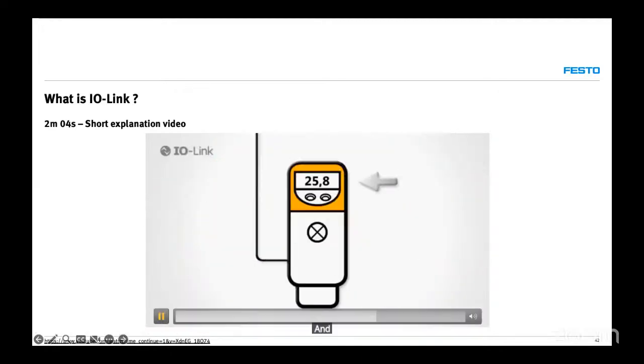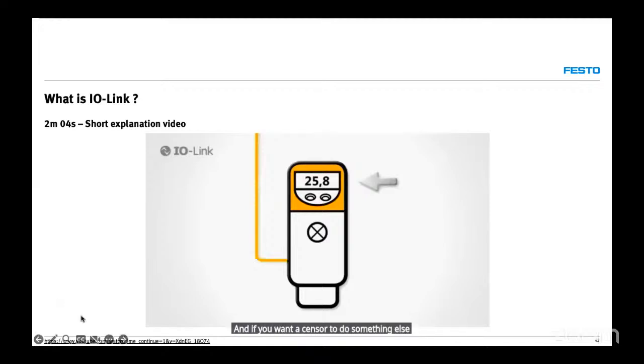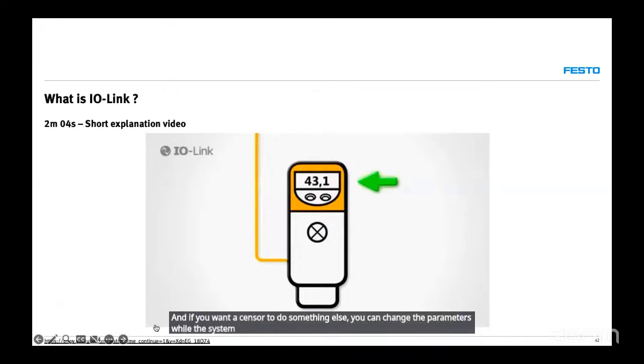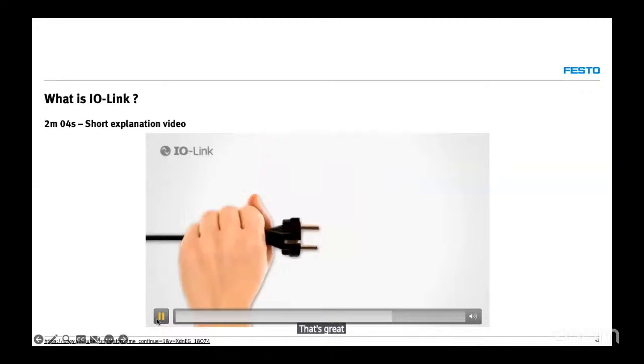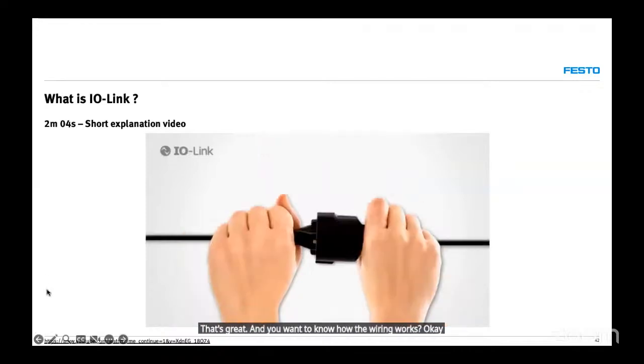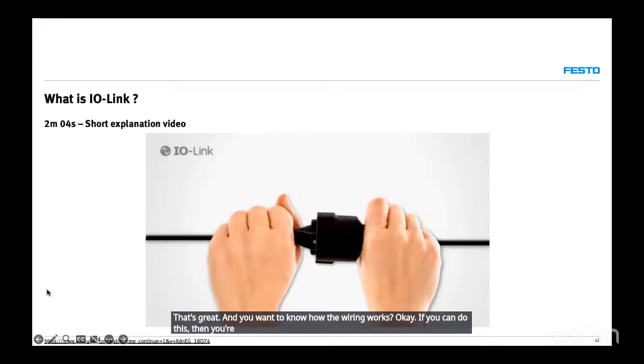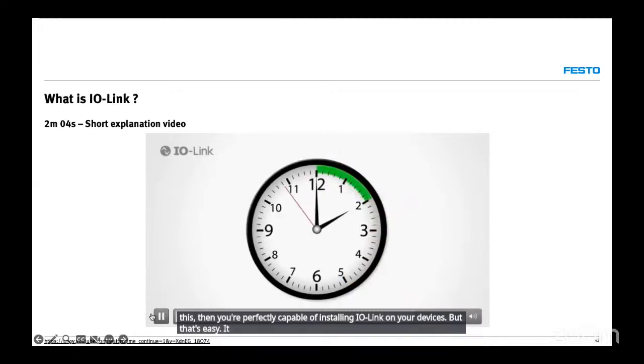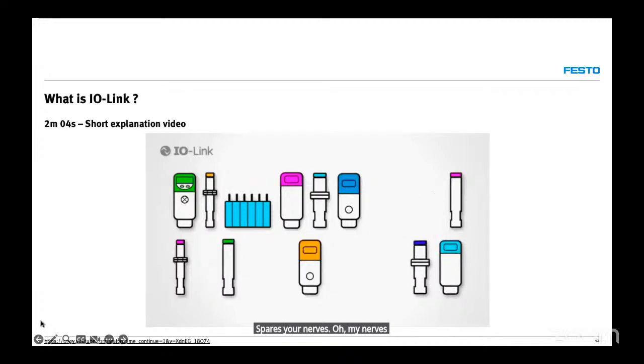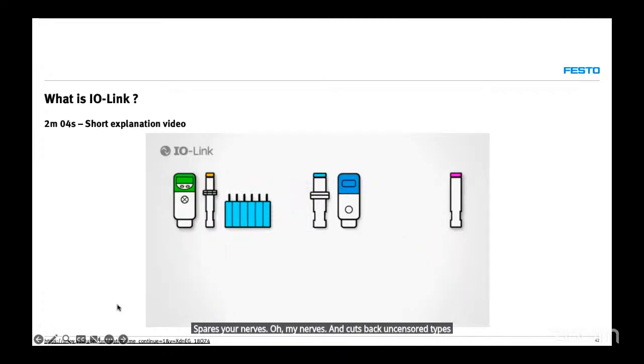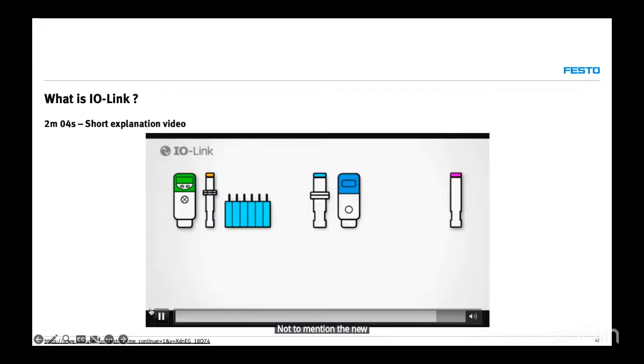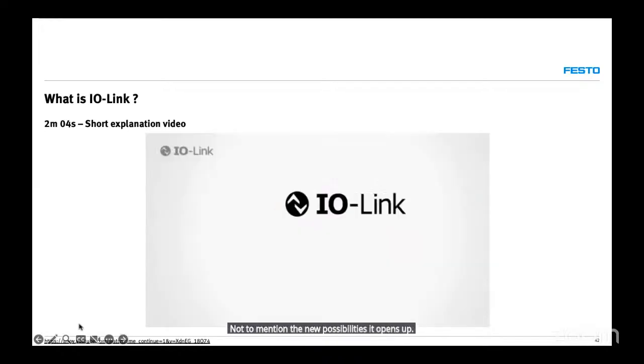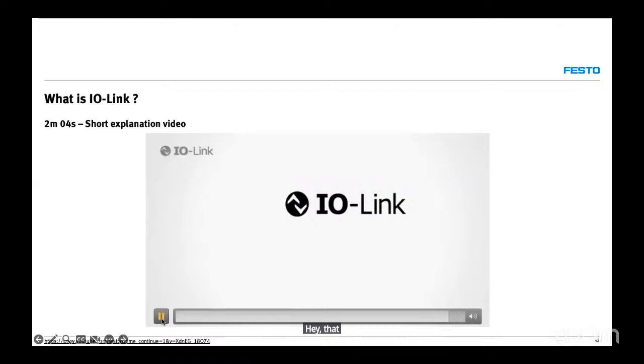If you want a sensor to do something else, you can change the parameters while the system is still running. Really? That's great. And you want to know how the wiring works? If you can do this, you're perfectly capable of installing IO-Link on your devices. It's easy, saves time, spares your nerves, and cuts back on sensor types. Not to mention the new possibilities it opens up for machine design. That's IO-Link. Universal. Move to the next one, please.